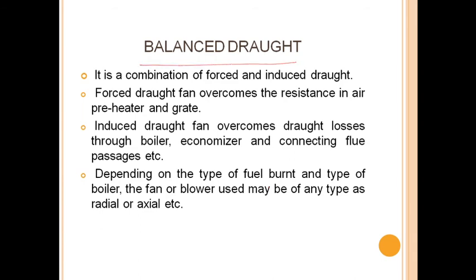Balanced draught is a combination of forced and induced draught. Forced draught fans overcome the resistance of the air preheater and grate, while induced draught fans overcome the draught losses through the boiler, economizer, and connecting flue passages. Depending upon the type of fuel burned and the type of boiler, the fans and blowers may be of any type — radial or axial, etc.